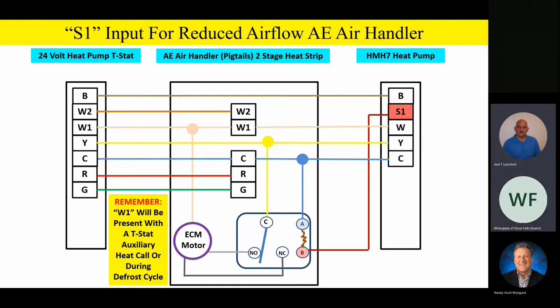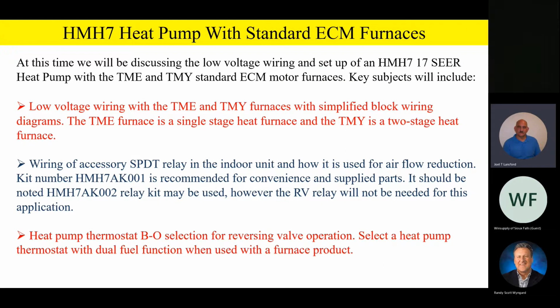Well, listen, let's go ahead and jump on in and talk about some furnaces then. So the TME and the TMY furnace: the TME is a single stage furnace and the TMY is a 2-stage heat furnace, but they both feature that standard ECM, that high efficiency motor. So what we're going to do is look at the low voltage wiring of both a TME and a TMY furnace with a simplified block wiring diagram, just like we did before. Now, please remember, you're still going to use that wiring accessory single pole double throw relay in the indoor coil for airflow reduction. And again, that kit number 001 is going to be recommended for convenience and supplied parts.